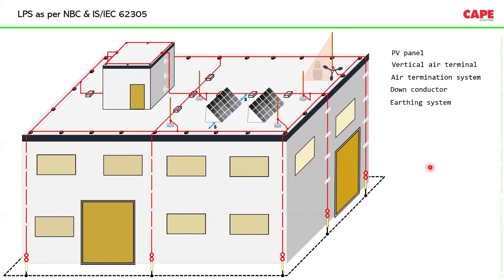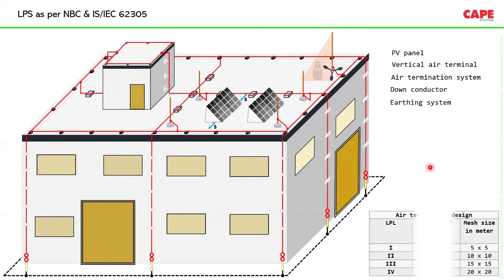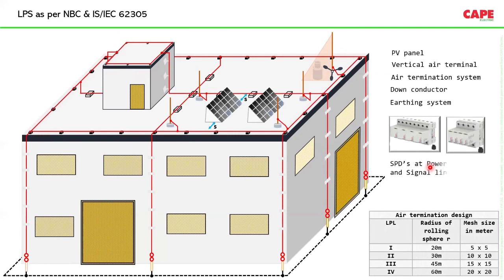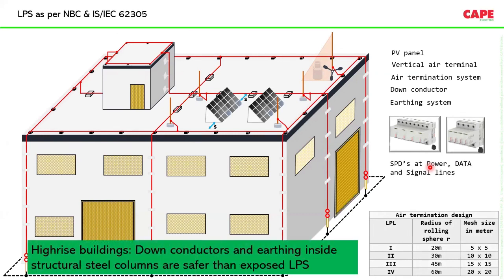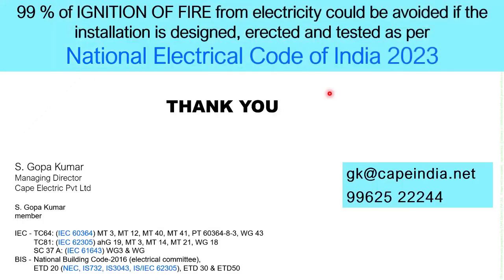Lightning protection must be carried out as per IS IEC 62305. Especially in hospitals, you must follow this particular standard, because the electromagnetics of the lightning can damage your electronic equipment. Now, a properly or well designed and installed lightning protection only can protect your electronic appliances. So with this, I would like to stop today's presentation. And as I said, 99% of the electrical accidents we are able to solve, or these accidents are avoidable.